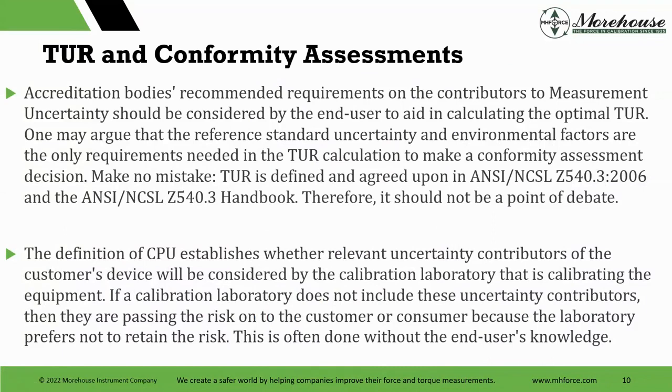They shop on who can do it. So everybody has different uncertainties, and some people can calibrate your devices and some people cannot. If the person's in purchasing, again, that scenario, maybe they don't know, and you might not be getting what you really need. And then we further go out to say, hey, not only might you not be getting what you may not need, that lab might give you conformity assessment based on manufacturer's tolerance.